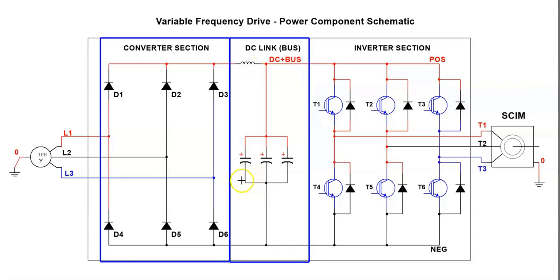These three devices here are capacitors. They're connected in parallel with the DC bus, and they filter out voltage ripple. And current is stored in those capacitors, so you have current available for sudden and quick motor changes. And they also store current when you have what's called generator action from the motor.